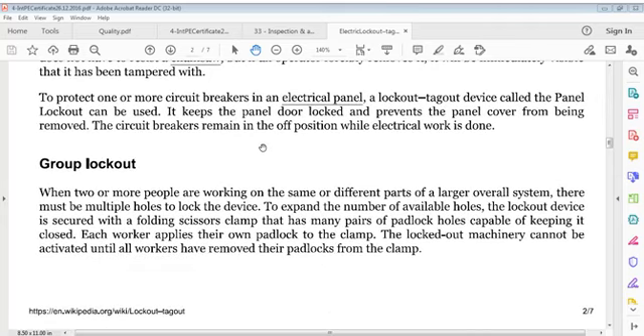To protect one or more circuit breakers in an electrical panel, a lockout tagout device called a panel lockout can be used. It keeps the panel door locked and prevents the panel cover from being removed. Circuit breakers remain in the off position while electrical work is done. Group lockout.